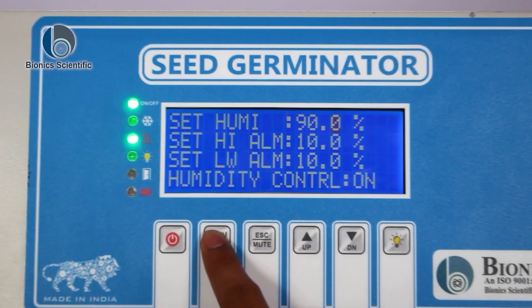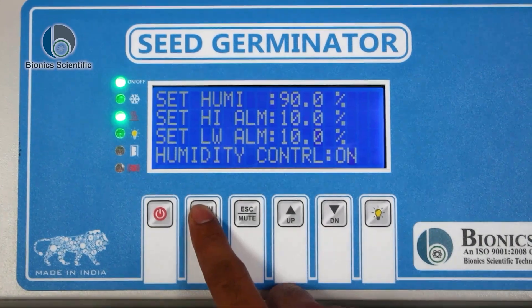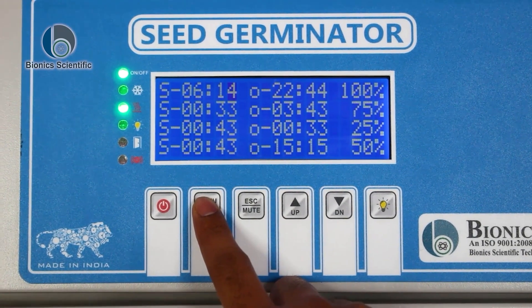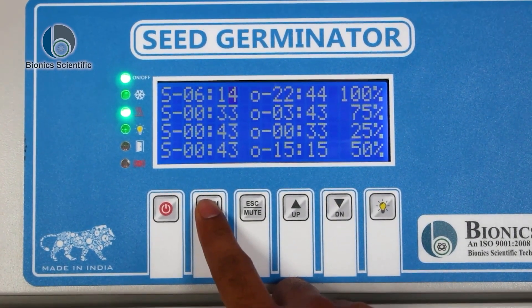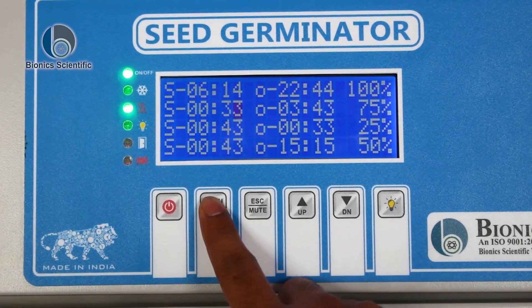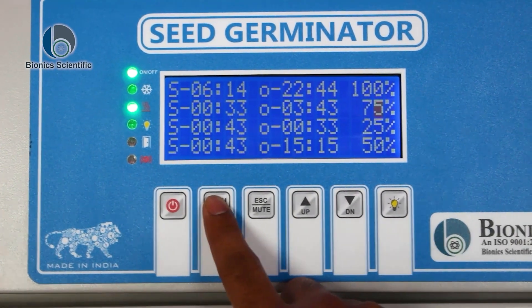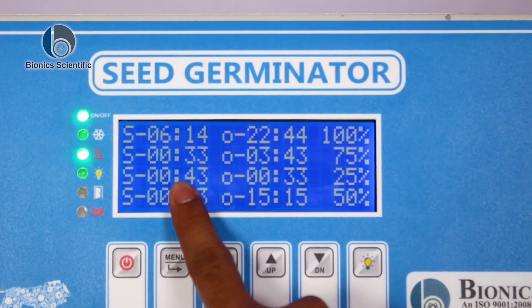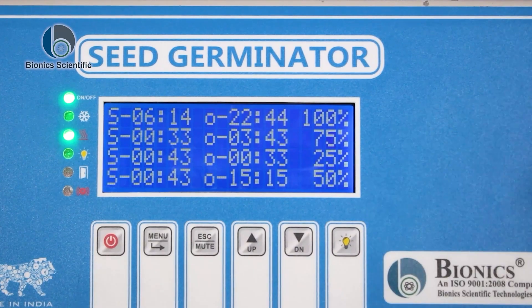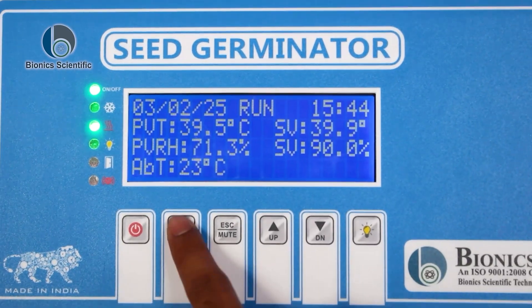Set humidity, set high alarm, set low alarm, humidity control on/off, data erase no, data USB no — please insert USB. These are the cycles present here. There are provisions for time, date, temperature, and humidity. As you can see, the time is mentioned and the lux is also present — 100%, 75%, 25%, 50%. These are the lux percentages set according to the cycles.